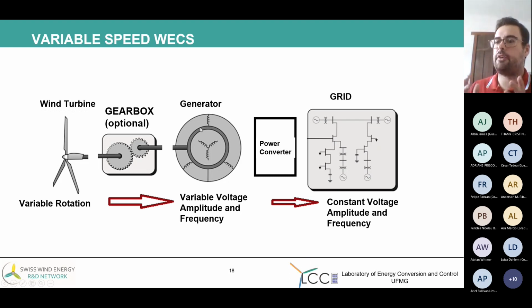But to work with variable speed, it's necessary that this generator works with variable voltage, amplitude, and frequency. If the voltage and frequency are variable, it is not possible to connect directly to the grid, because the grid has constant voltage, amplitude, and frequency. The objective of the power converter is to convert this voltage. We convert the variable voltage, amplitude, and frequency to a constant voltage, amplitude, and frequency to feed the electrical energy to the grid.